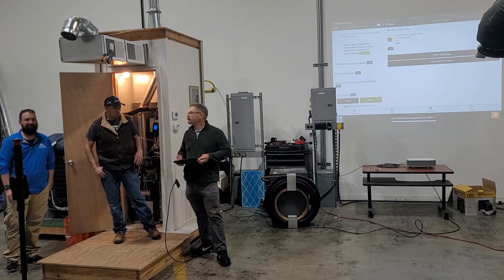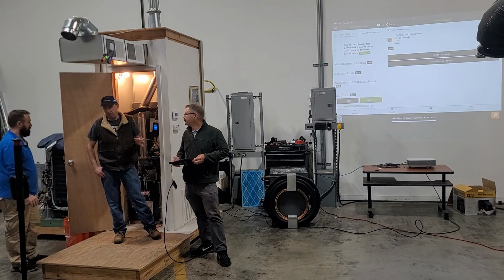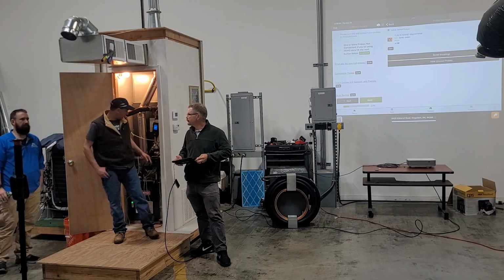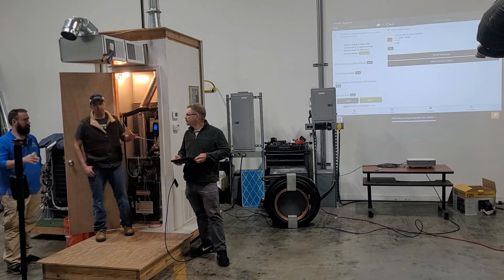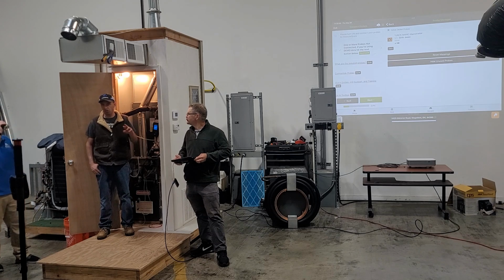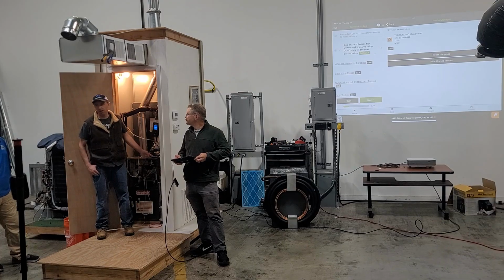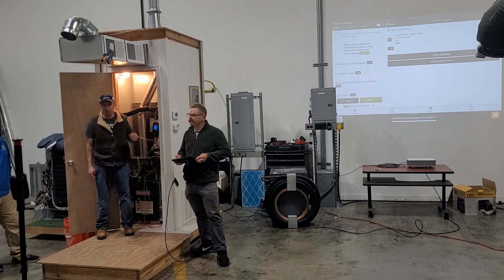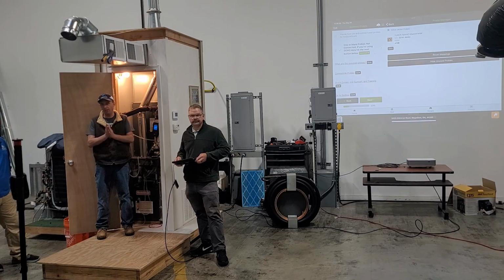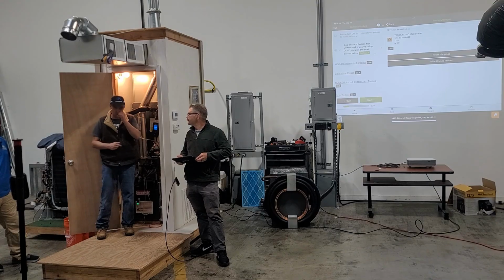So there is one advantage to using single port manometers. When you're using this dual port, all you're seeing is total stack, the difference between supply and demand. You don't see individual measurements. There's only one sensor in a dual port manometer, the Testo and the Yellow Jacket, so all it can see is two ports. It cannot compare the two.